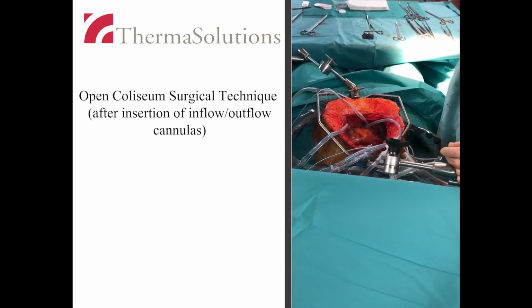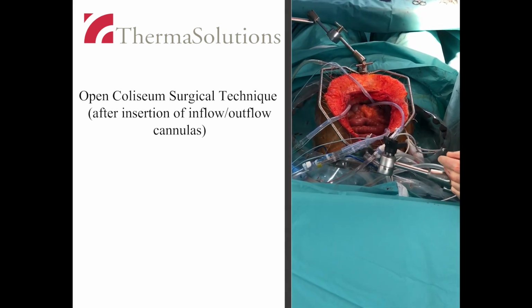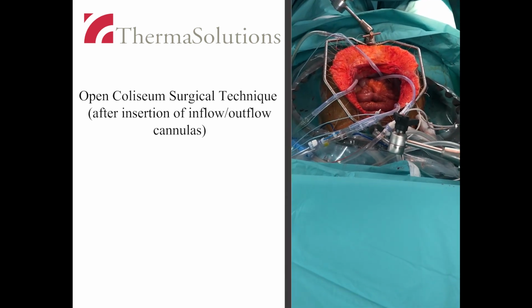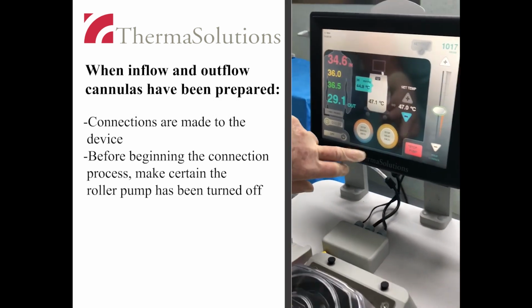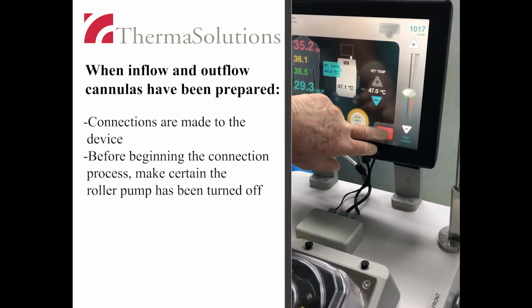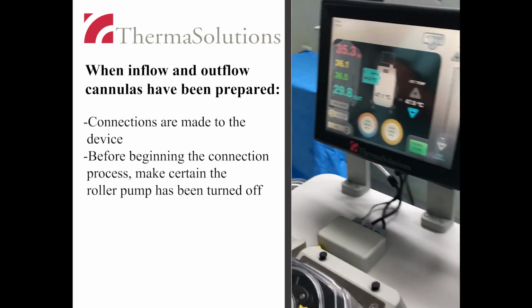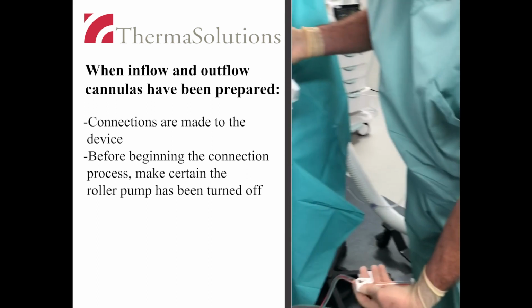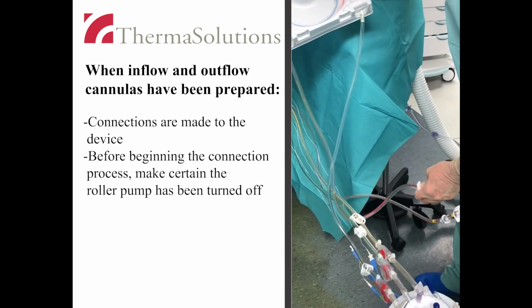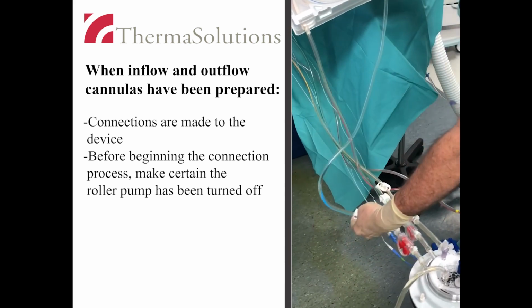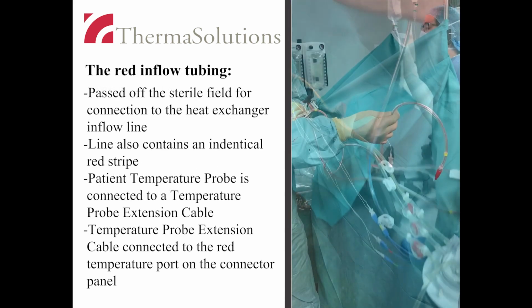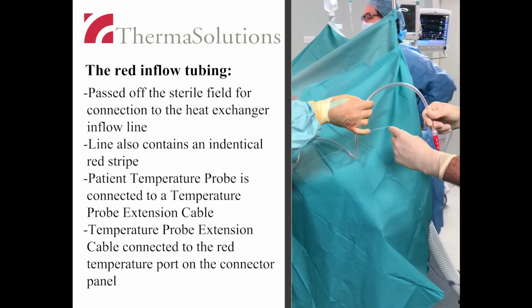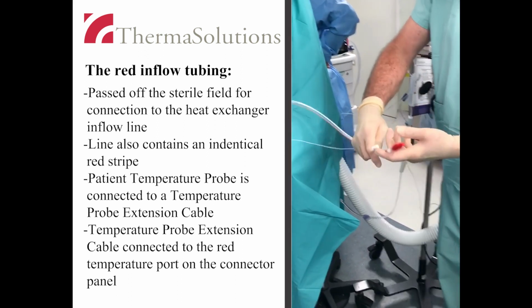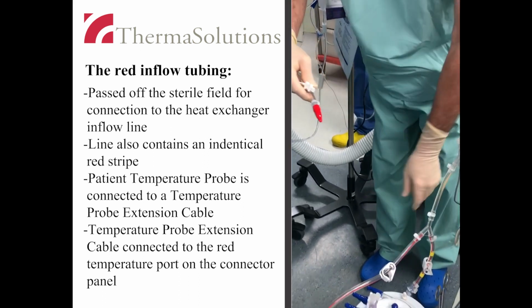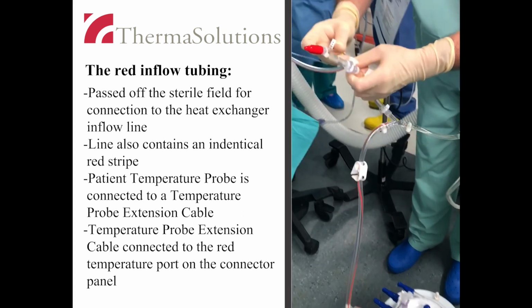Pictured here is the open Coliseum surgical technique after insertion of inflow-outflow cannulas into the patient. After the inflow and outflow cannulas have been prepared, connections are made to the device. Before beginning the connection process, make certain the roller pump has been turned off and the tubing is clamped. The red inflow tubing is passed off the sterile field for connection to the heat exchanger inflow line. This line also contains an identical red stripe.